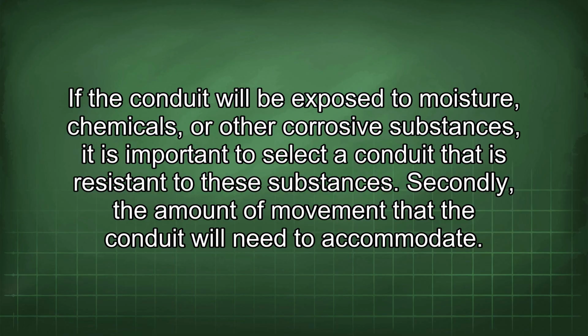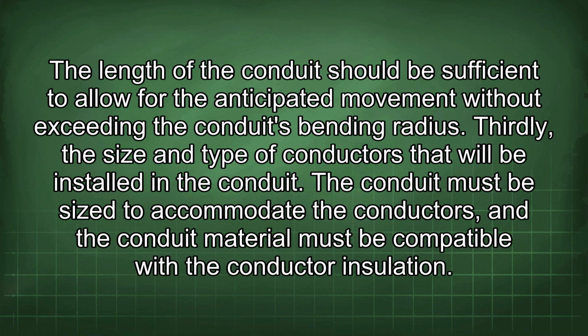Secondly, the amount of movement that the conduit will need to accommodate. The length of the conduit should be sufficient to allow for the anticipated movement without exceeding the conduit's bending radius. Thirdly, the size and type of conductors that will be installed in the conduit. The conduit must be sized to accommodate the conductors, and the conduit material must be compatible with the conductor insulation.